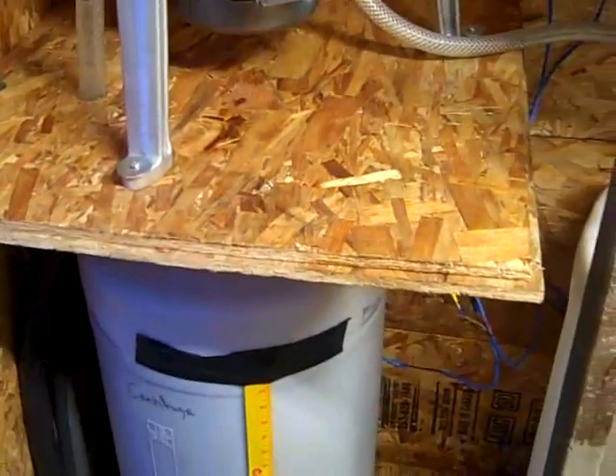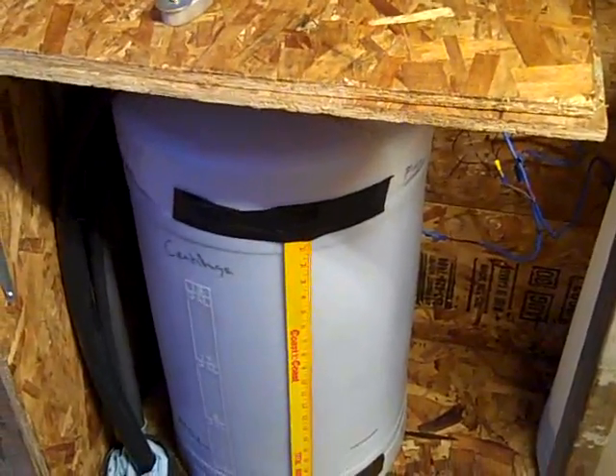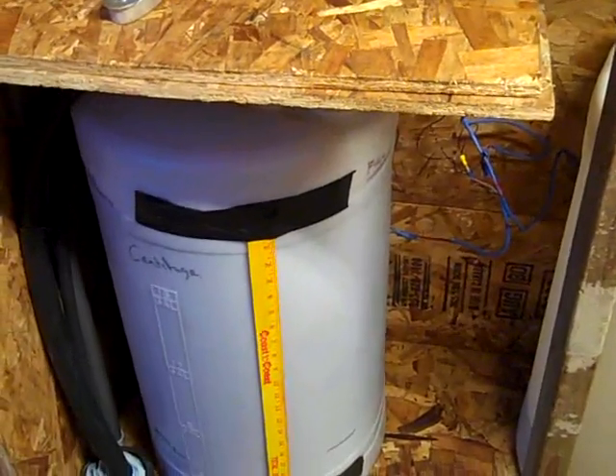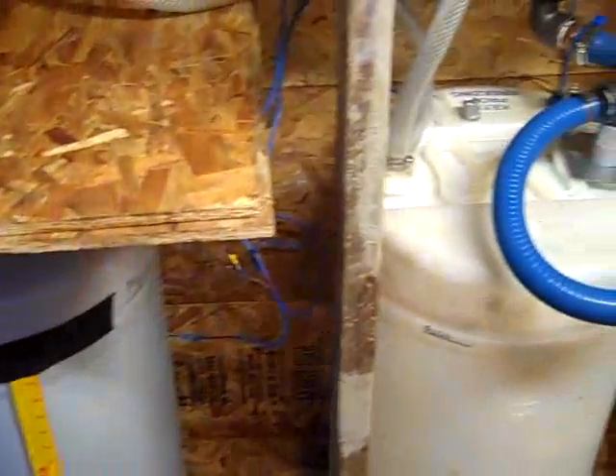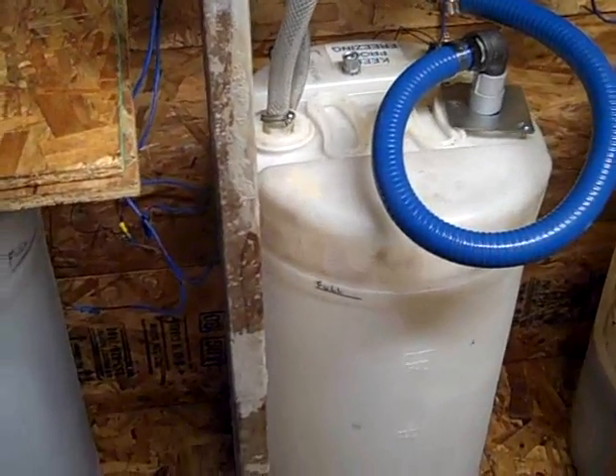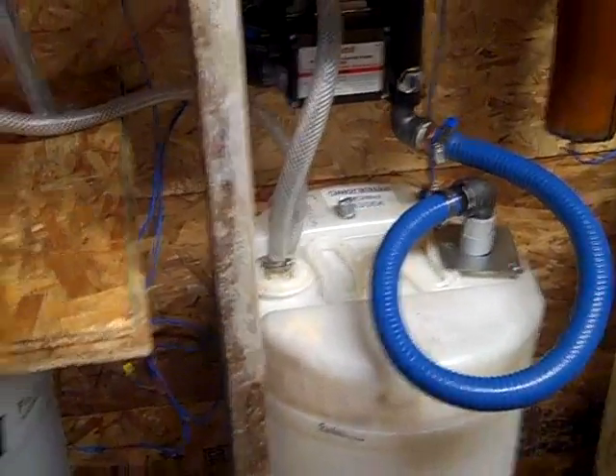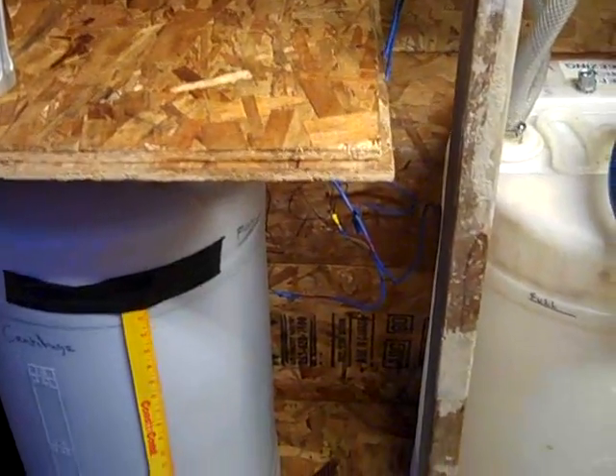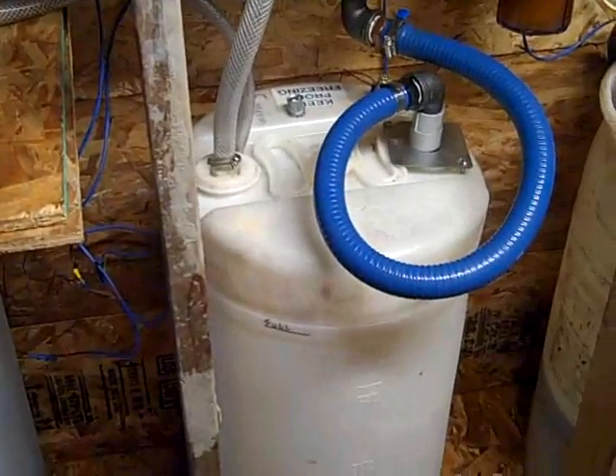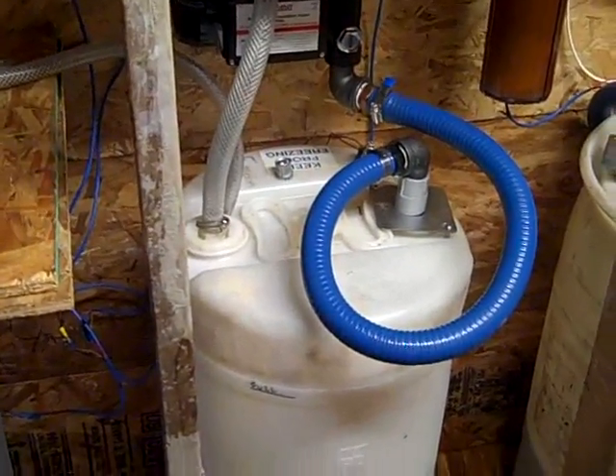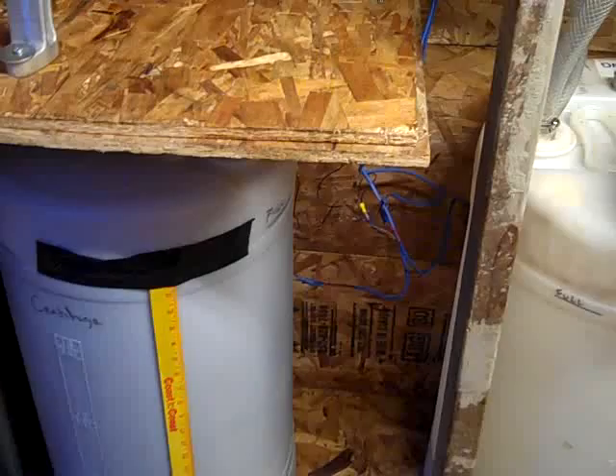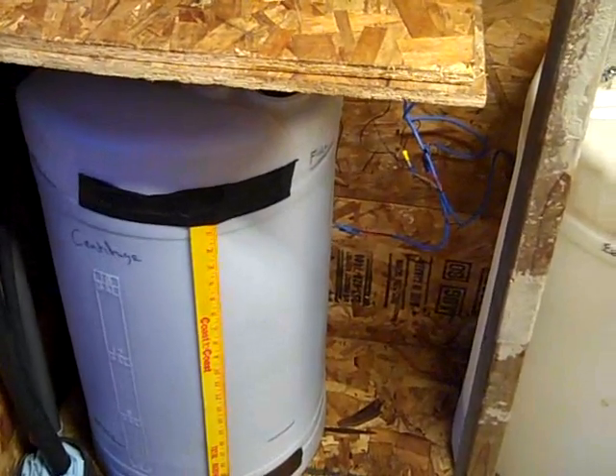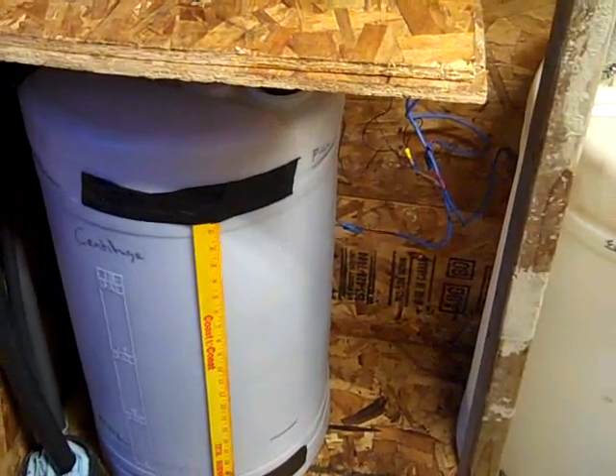So if it's activated by either float, then it will run. There's also another float in this particular barrel that will control the secondary pump. So I have 3 floats controlling this secondary pump. The one in this last barrel is a safety switch, and the ones in this secondary barrel and the gravity barrel, of course, are operating. So if this final barrel here is full, the secondary pump will not pump oil anywhere.